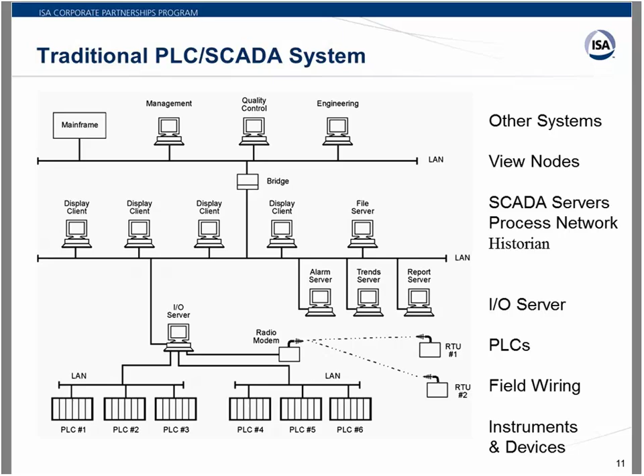Now, let's take a look at what a DCS system looks like. You'll see a very similar structure, but there's usually not as many moving parts. Traditionally, a DCS is usually a single vendor. There's a controller, which is implemented into the servers as well. It all comes from one programming environment. At the bottom, you still have your instruments and devices. You have field wiring, then you have controllers. You have a process network, just like the SCADA system. Usually that network is a little bit more integrated. You'll have various servers. You'll have a historian.